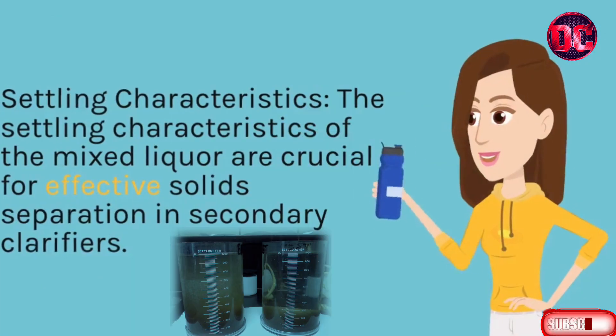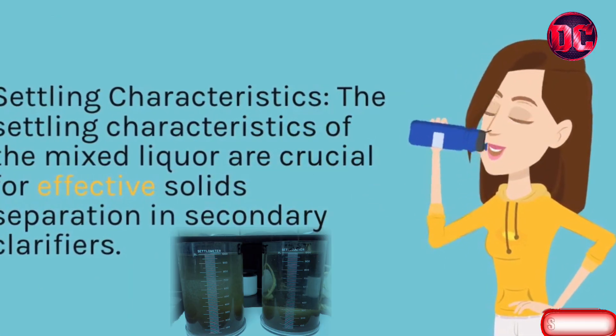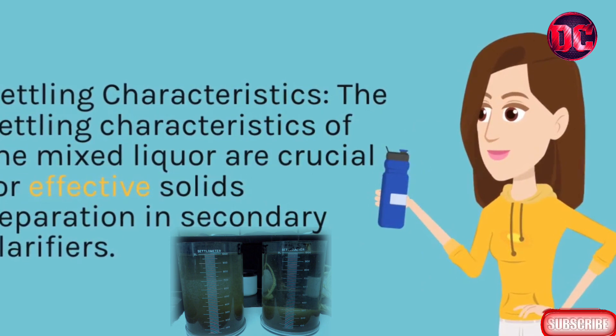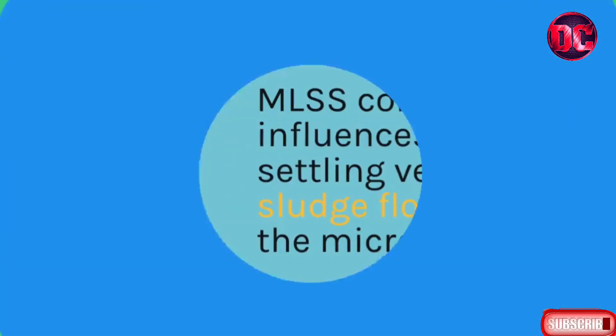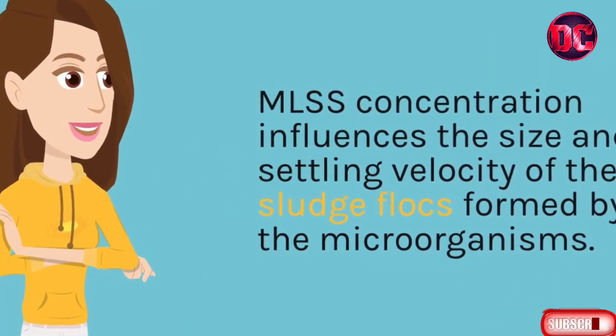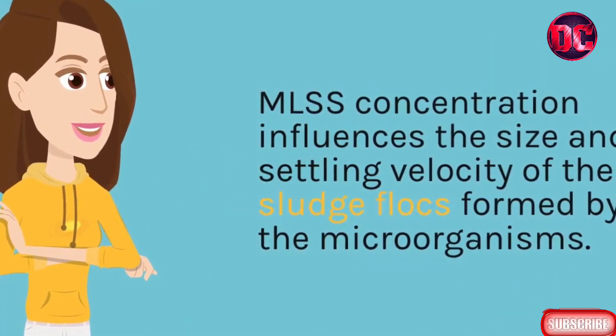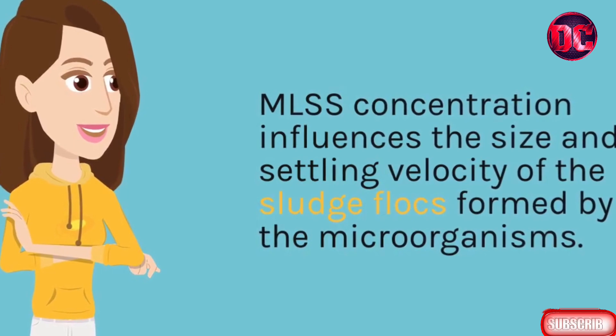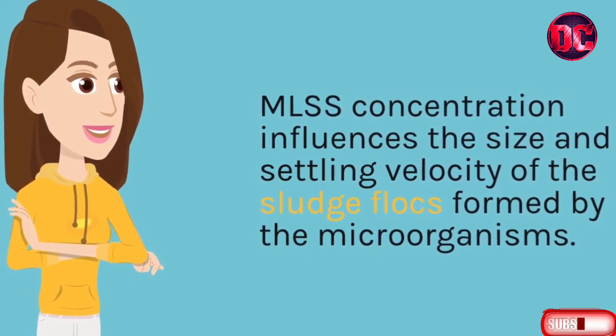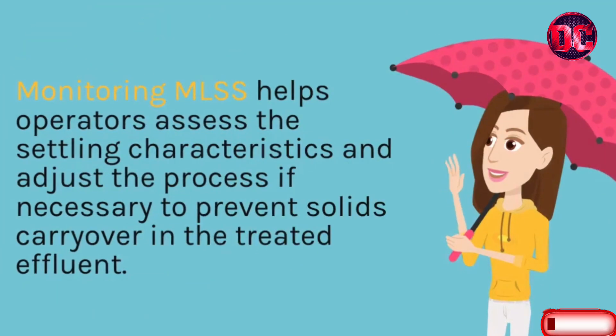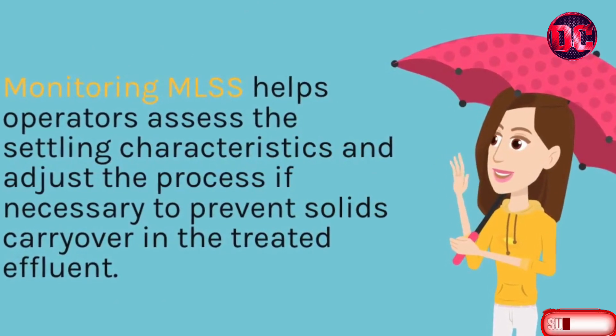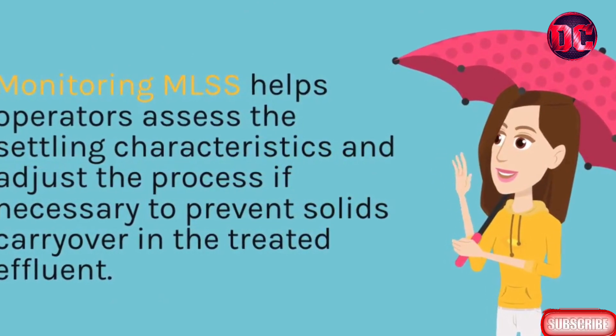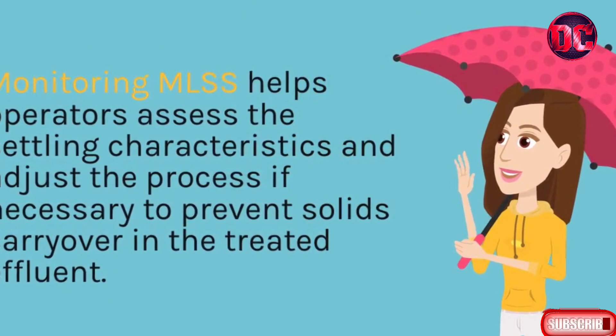The settling characteristics of the mixed liquor are crucial for effective solid separation in secondary clarifiers. MLSS concentration influences the size and settling velocity of the sludge flocs formed by the microorganisms. Monitoring MLSS helps operators assess the settling characteristics and adjust the process if necessary to prevent solids carryover in the treated effluent.